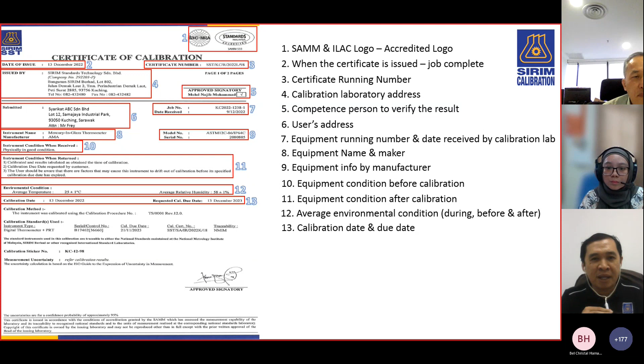So if your management or the auditor asks why you put a 2-year due date, or why this due date column is blank, you can answer that this equipment is used as a reference only, as our standard to verify our equipment. Then you prepare a form saying you use it only on certain dates, maybe once every 2 months or once every 3 months. Then it should be no problem to put a calibration due date of more than 1 year.